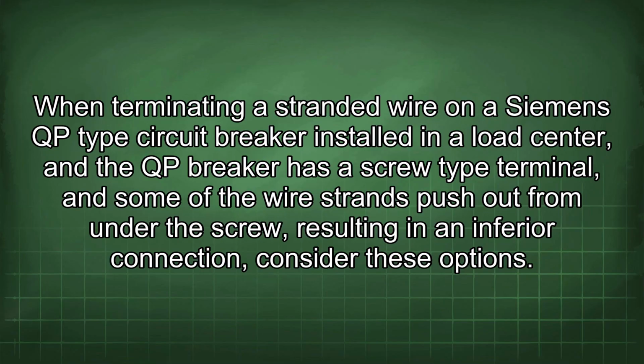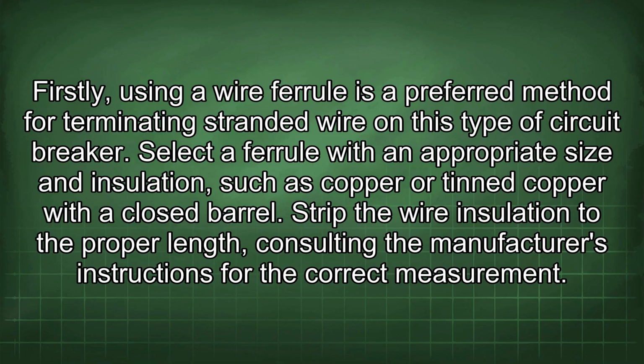When terminating a stranded wire on a Siemens QP-type circuit breaker installed in a load center, and the QP breaker has a screw-type terminal, and some of the wire strands push out from under the screw, resulting in an inferior connection, consider these options.